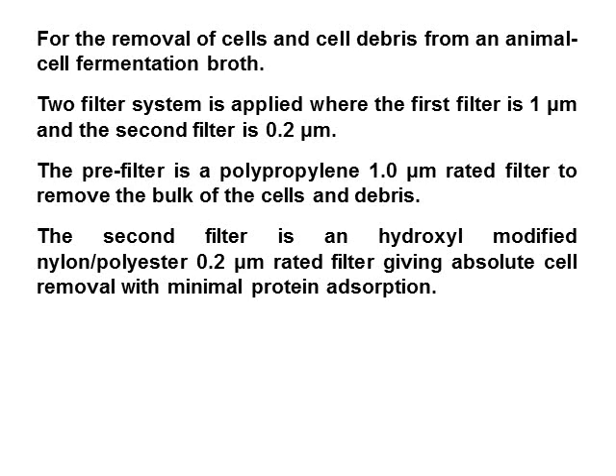For the removal of cells and cell debris from an animal cell fermentation broth, a two-filter system is applied. The first filter is a polypropylene 1-micron rated filter to remove the bulk of cells and debris. The second filter is a hydroxyl-modified nylon/polyester 0.2-micron rated filter, giving absolute cell removal with minimal protein adsorption.